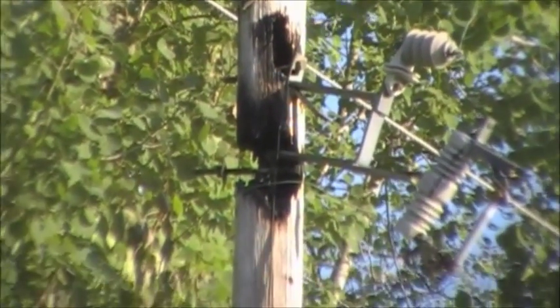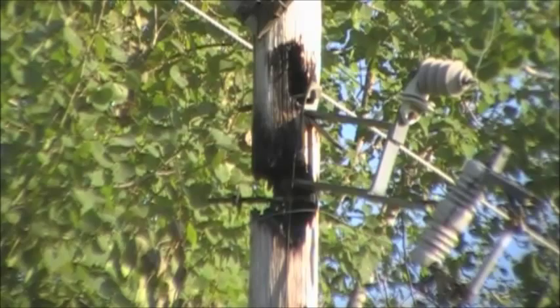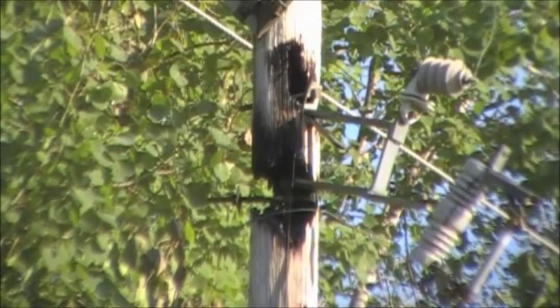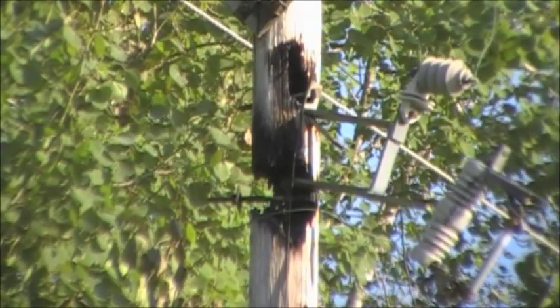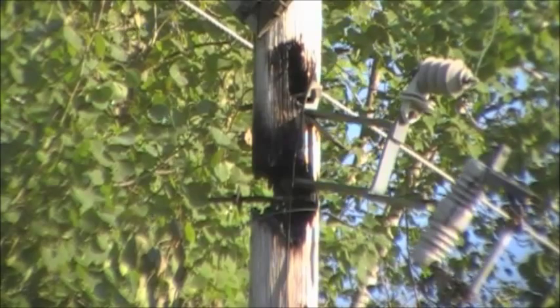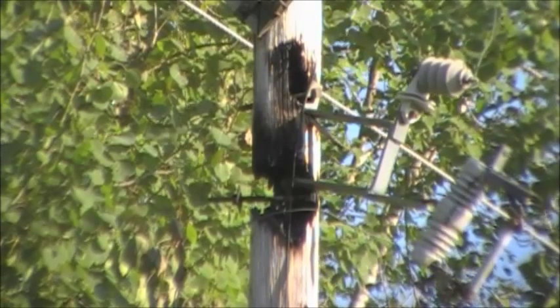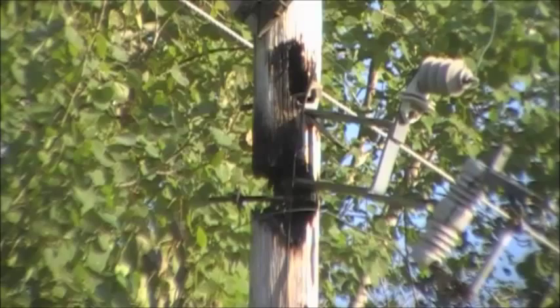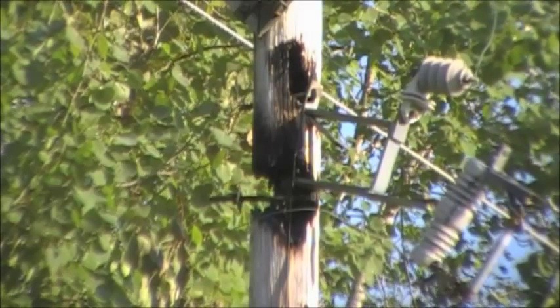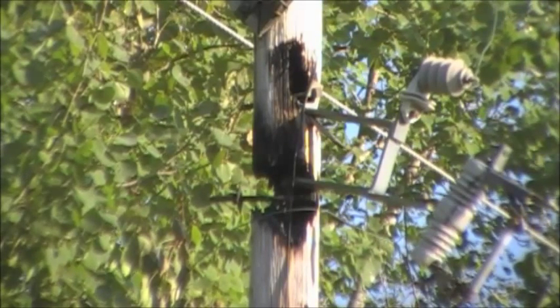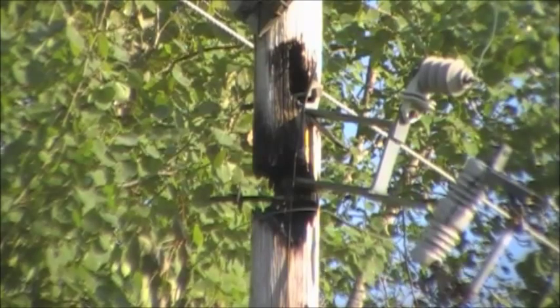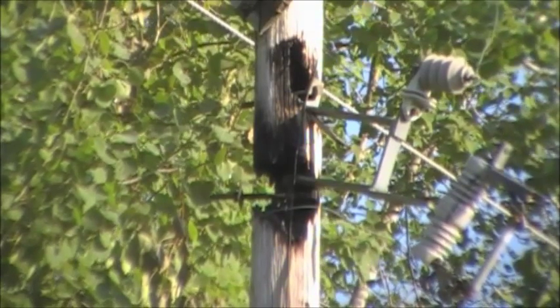Now this didn't happen in one event. This has been slowly going on and is still going on, because I can still hear the arcing at 120 hertz, as I explained earlier. 120 hertz, as verified on the scope at 125 hertz, and that is slowly burning its way through that utility pole, and it's burned better than halfway through.